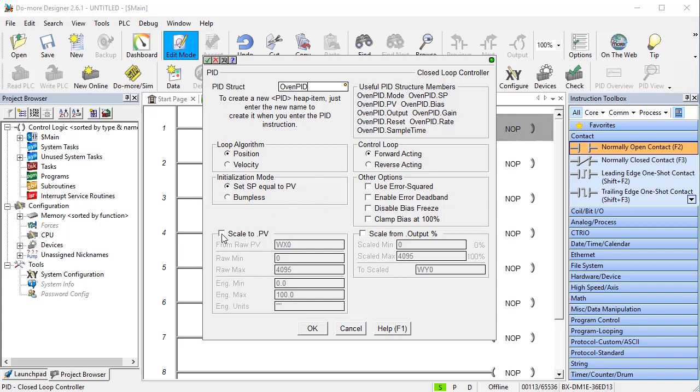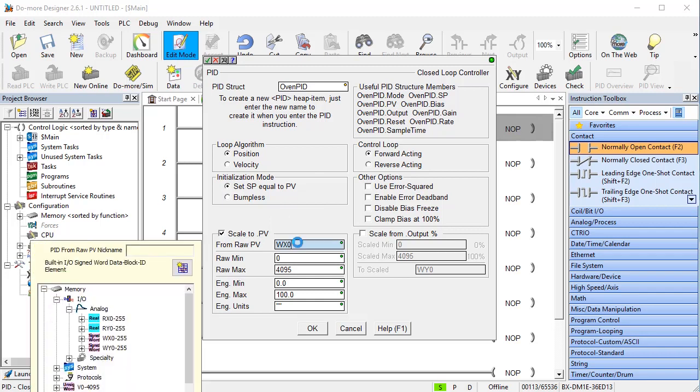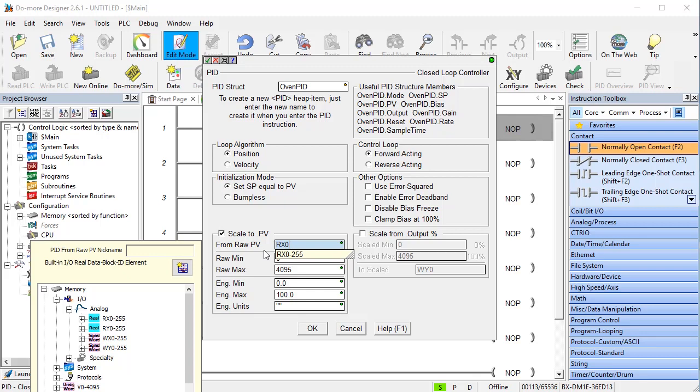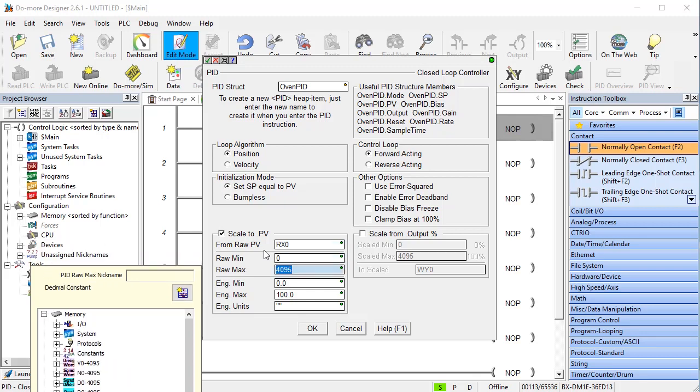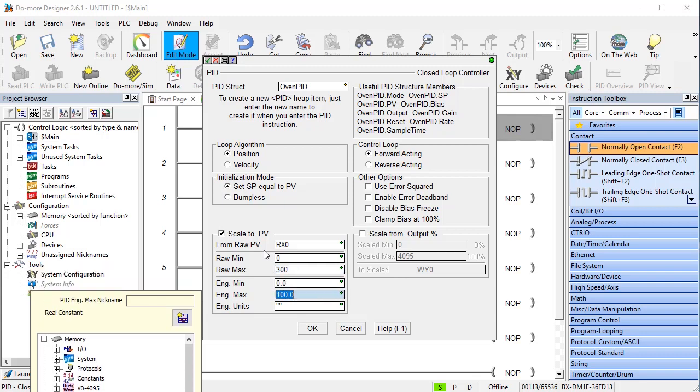We already scaled the process variable in the analog input dialog. But I'm going to do it here again anyway just so I can specify that I want the process variable to come from RX0. Otherwise, we would have to transfer RX0 to the process variable ourselves in the ladder code, right? So we've already scaled it to 0 to 300 degrees, so we'll scale it to that, which is no scaling.